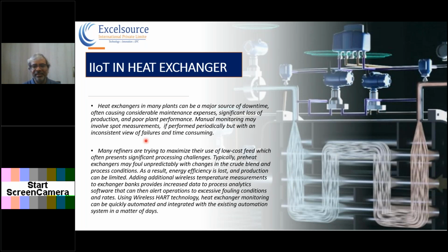So if temperature transmitters and pressure transmitters are installed across the heat exchangers, we get to know at what pressure and at what temperature it is operating, get the data collected, and keep monitoring everything on a regular basis. With IoT, we get to know that the performance of the heat exchanger started deteriorating from one particular point in time. This will help us identify when this particular heat exchanger has to go for CIP, cleaning in place, and then improve the performance back to normal.